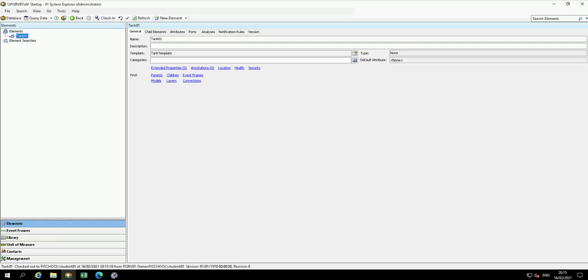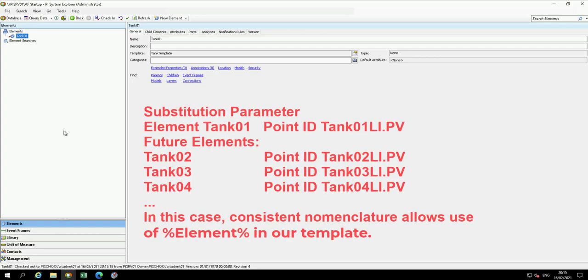Now we briefly discussed substitution parameters in the previous lesson. Substitution parameters can be confusing at times, so we'll briefly review their usage in this template and attribute. In this case, the level tags were previously created with a defined nomenclature: element name including the tank number, followed by LI dot PV, where LI is the level indicator and PV denotes process variable.